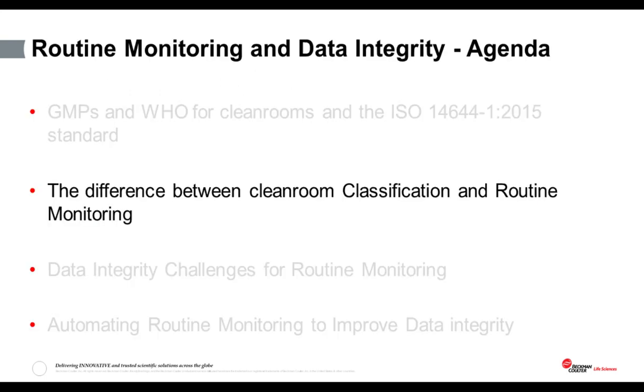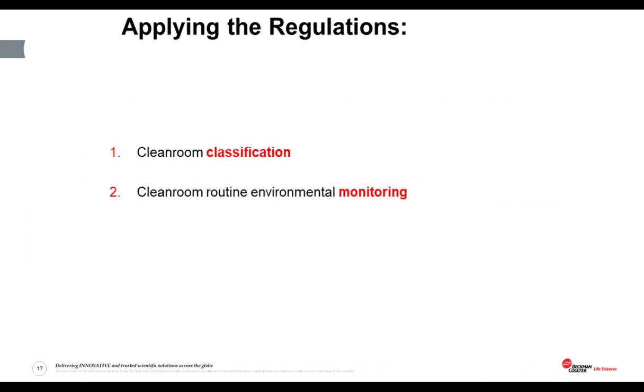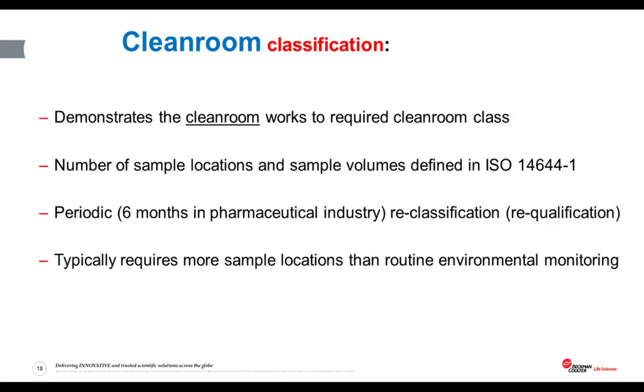So that's the rules and regulations. Now let's look at the difference between clean room classification and routine monitoring — they are two very different things. Portable particle counters are used for both applications. The classification process is defined very clearly in the ISO standard, whereas it is the responsibility of the user to define the routine environmental monitoring program specific to their own production process, product, and clean room. This absence of specific guidance for routine monitoring locations and frequencies often leads users to wonder what they should be doing.